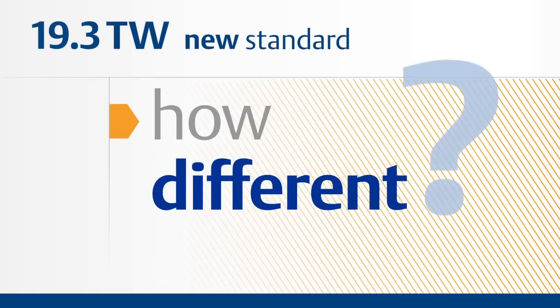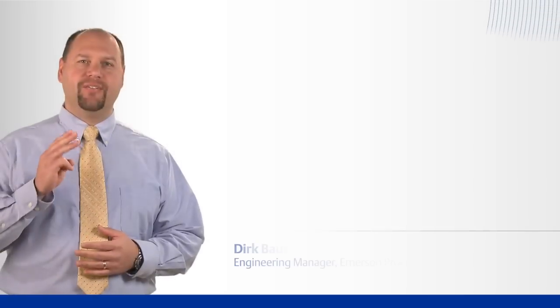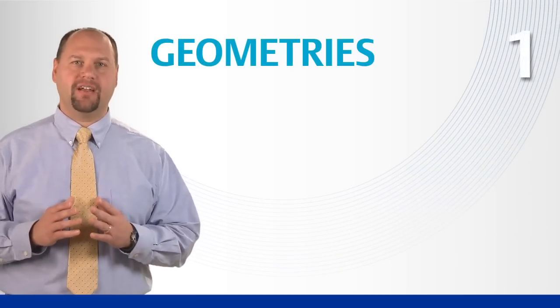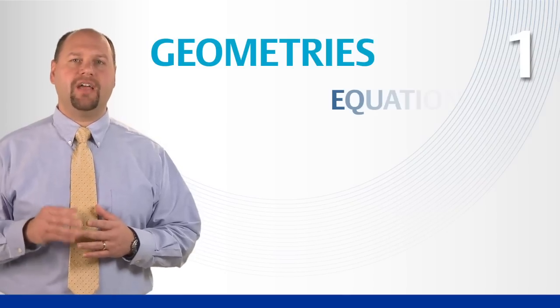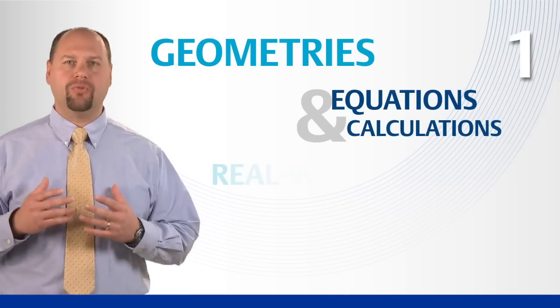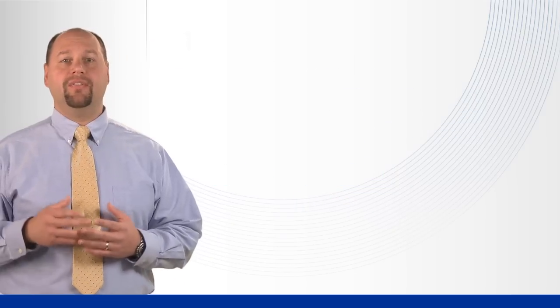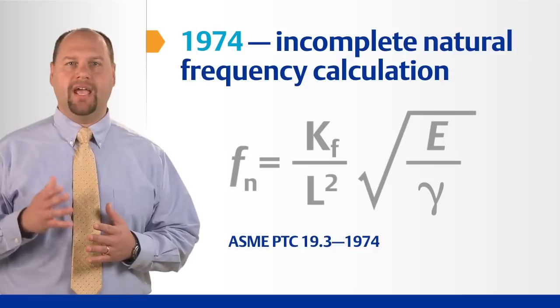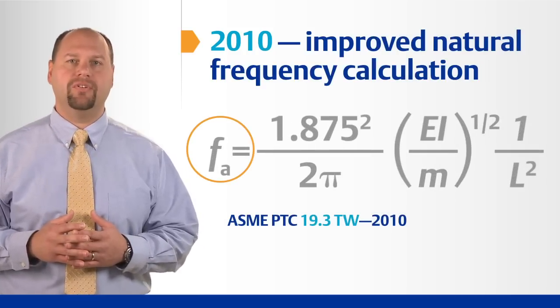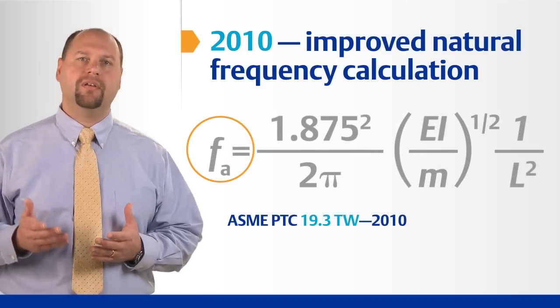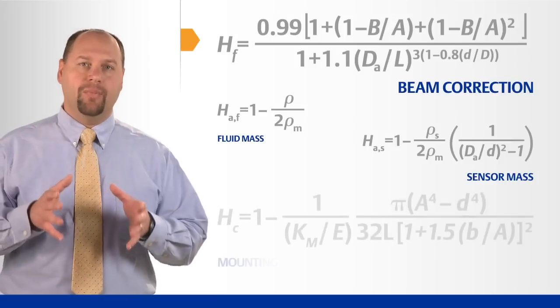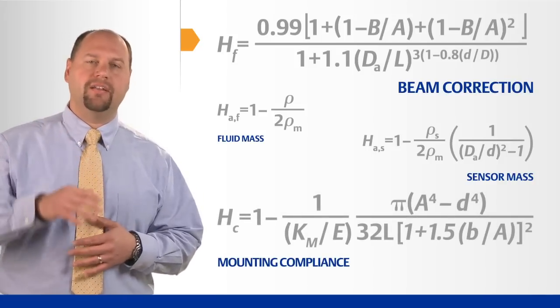So how is the new standard different? There are three key differences. First, the new standard includes stem profiles previously not covered, and more accurate natural frequency equations that reflect the real-world effects resulting from installation. The ideal or theoretical natural frequency is corrected for the effects of adding a sensor and the mounting style. This lowers the effective natural frequency that is compared to the shedding frequency. Many factors such as beam correction, fluid mass, sensor mass, and mounting compliance are calculated and applied to the natural frequency.